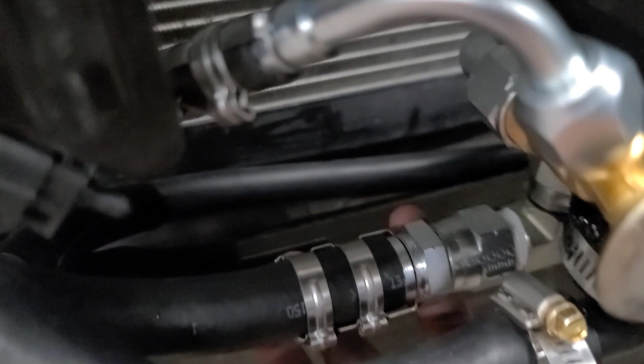So I got the high side line leak situated. Then I found out I had a low side line leak. Let me show you where that leak was coming from - it was actually coming from this little area here. I pretty much just removed the line, made sure I had it installed correctly, and put some Teflon tape on the threading, and that seemed to have fixed the leak to where it passed the leak test. So we're good there.